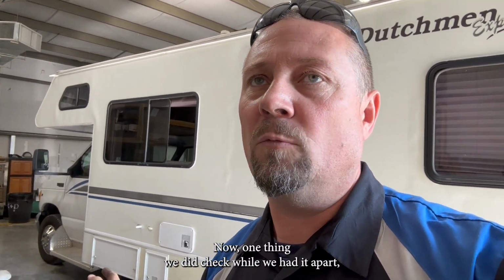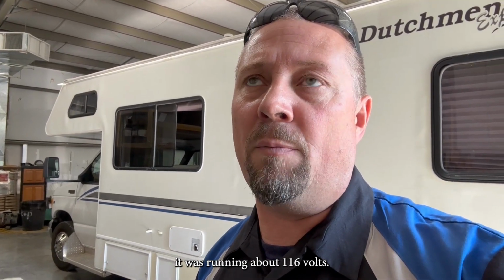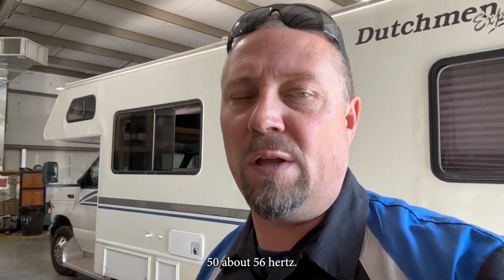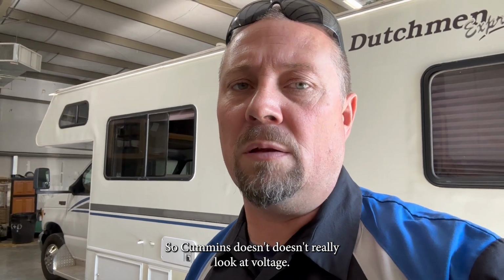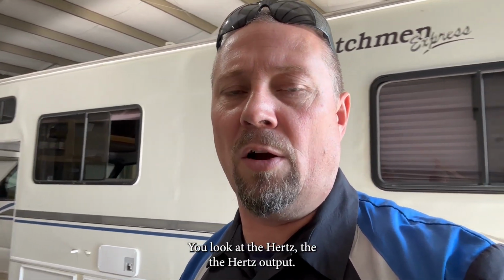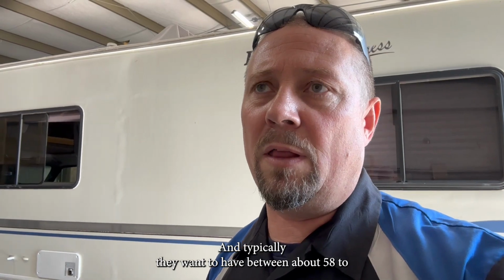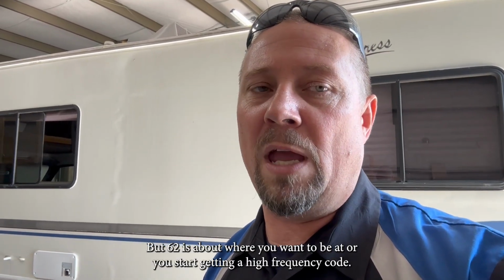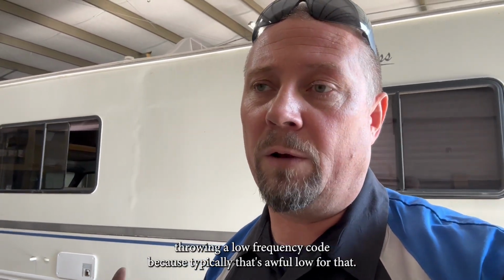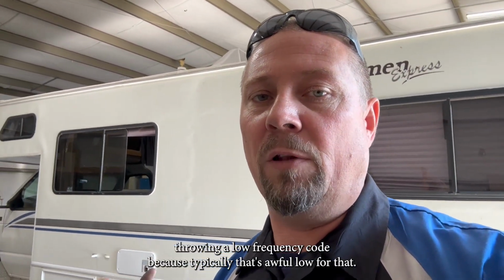Now, one thing we did check while we had it apart, it was running about 116 volts, about 56 hertz. So Cummins doesn't really look at voltage, they look at the hertz output. And typically they want to have between about 58 to 62, sometimes 63. But 62 is about where you want to be, or you start getting a high frequency code. I'm surprised that one wasn't throwing a low frequency code, because typically that's awful low for that.